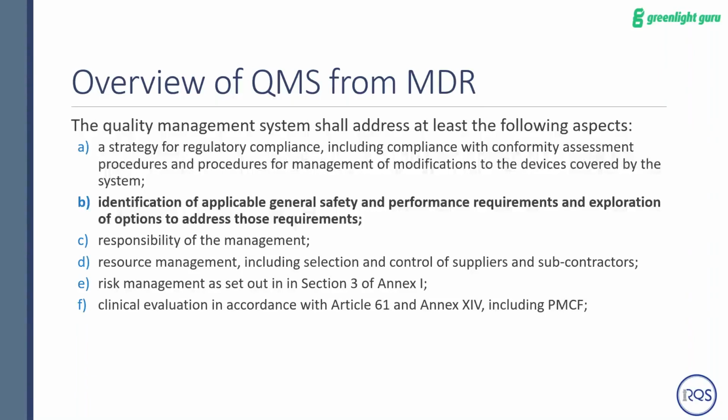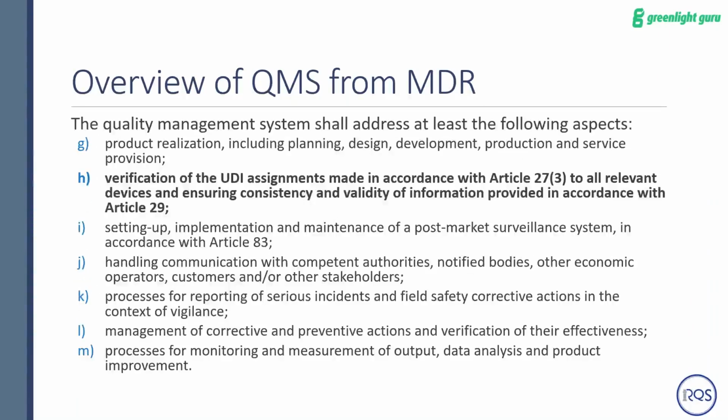So this is obviously the general safety and performance requirements and how new those are, making sure you comply with those. Other big one is UDI. So previously Europe did not have UDI requirements. There are plenty of companies in the US that are already complying with that. There are some differences, but if you just have a CE mark or EU based quality system, then this is new to you. You need to implement those procedures and get compliant with UDI for your devices.